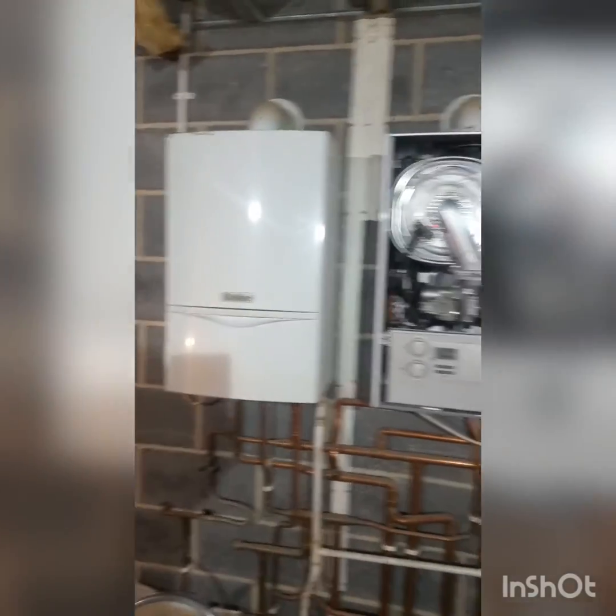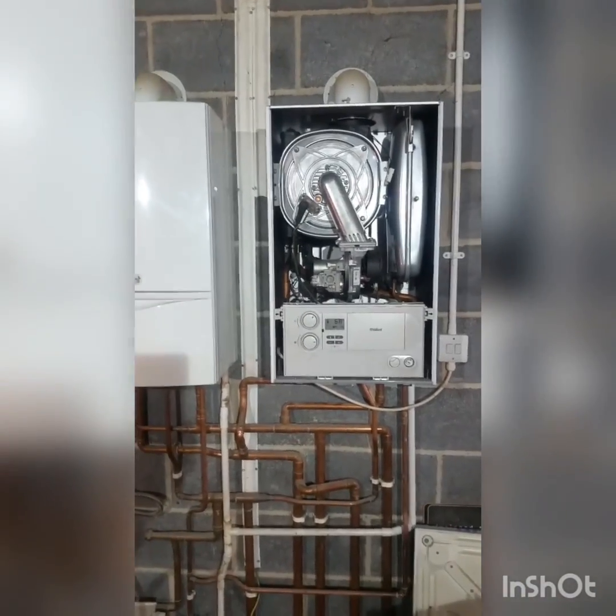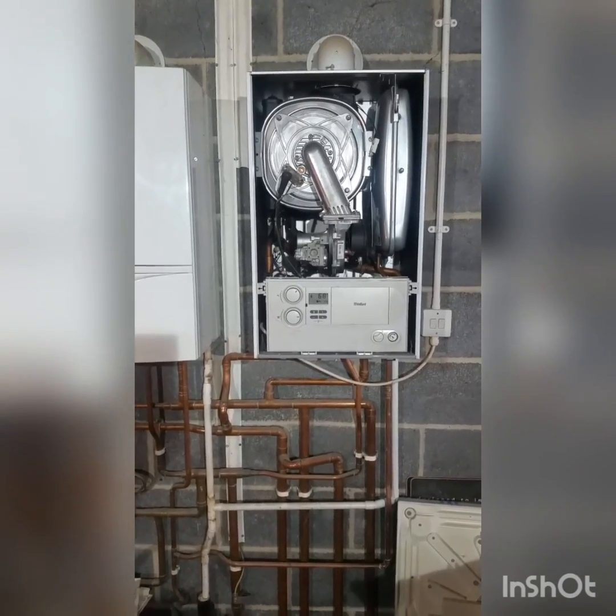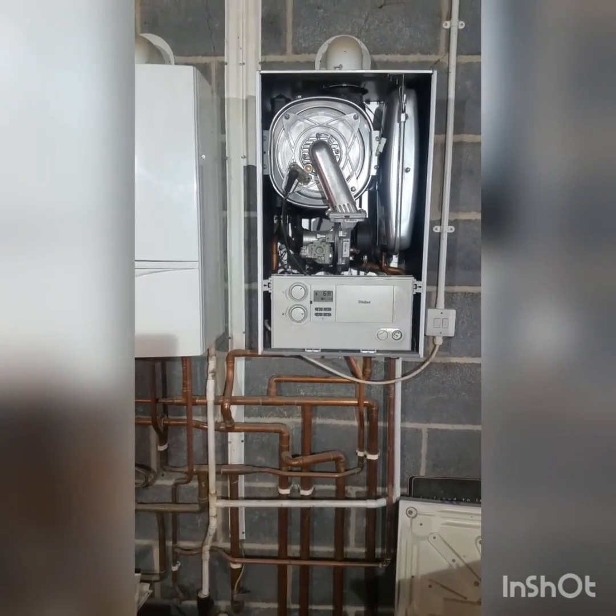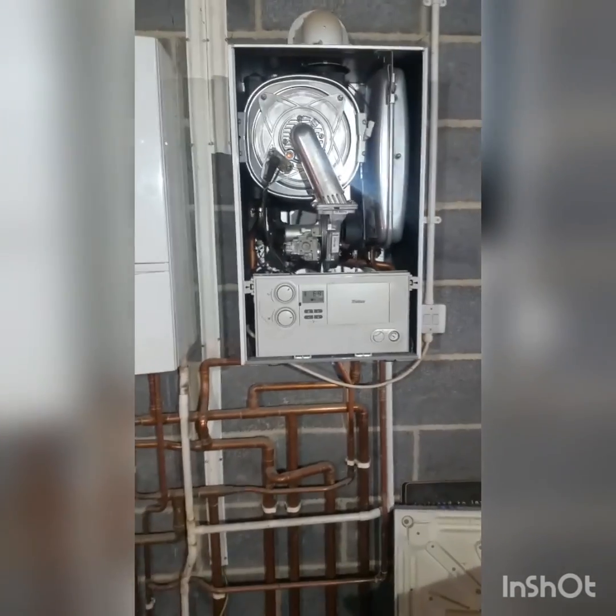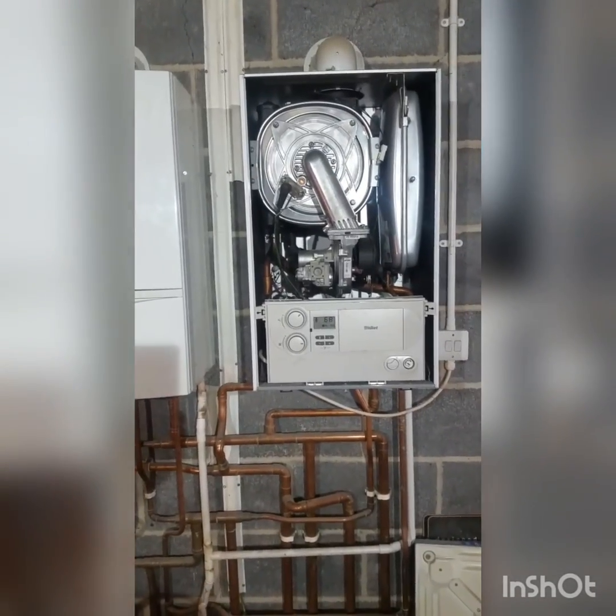Interesting job. I've got a pair of Vaillant 24 kilowatt system boilers. Customer called, had problems with the pressure loss. Found the heat exchanger on the right hand boiler had failed, so here it is down here.